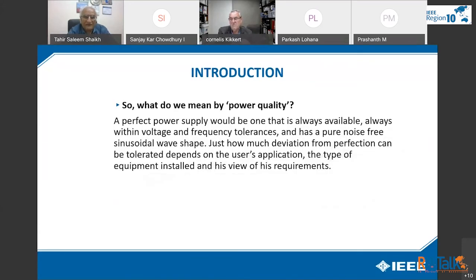So what do we mean by power quality? A perfect power quality supply should be one that is always available, always within voltage and frequency tolerance, that is plus or minus 2% for frequency as per the IEC code and plus or minus 10% for voltage, and has a pure noise-free sinusoidal wave shape. Just how much deviation from perfection can be tolerated depends on the user's application, the type of equipment installed, and his view of his requirements.